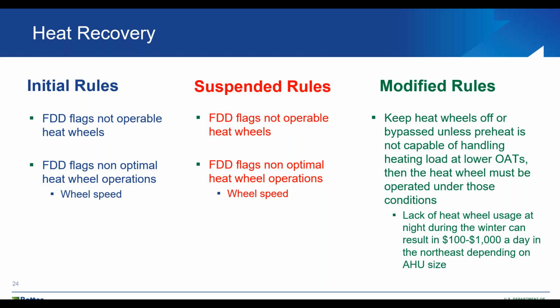I once had a customer that had a heat recovery system that was costing them over $1,000 a day during the winter time because it wasn't operating effectively. However, it had the benefit that they had a heating coil that was sized properly. So even though it wasn't working, they were able to maintain the heating in there. So the people downstream were not concerned with heating. So this is one of those that you have to be concerned with.